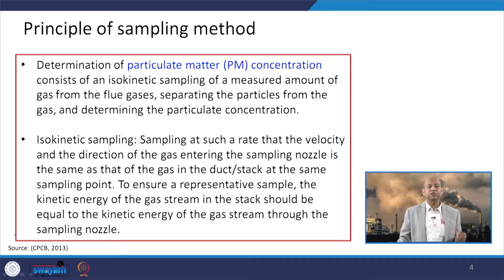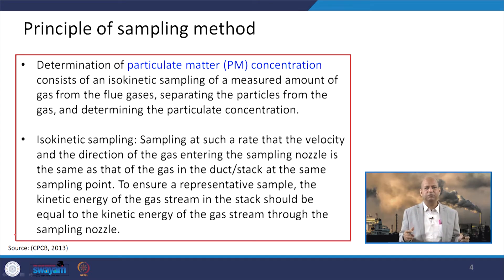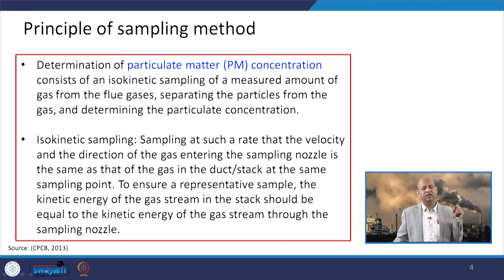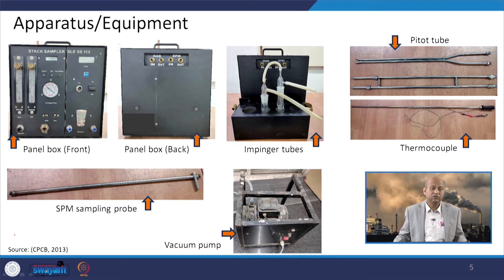The principle of the sampling method for particulate matter monitoring is basically the isokinetic sampling method, which is given a lot of emphasis. In this method, we have to ensure that the velocity, temperature, and other parameters at the nozzle used for extracting the sample are the same as those in the stack. The velocity, flow rate, and all kinetic parameters going into the probe or nozzle must match those in the entire stack — that is the fundamental isokinetic requirement.